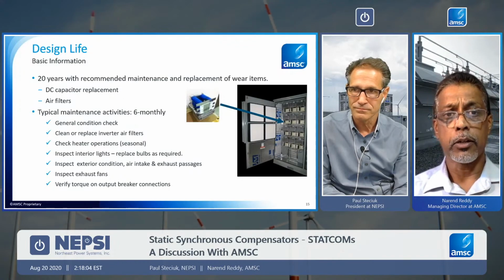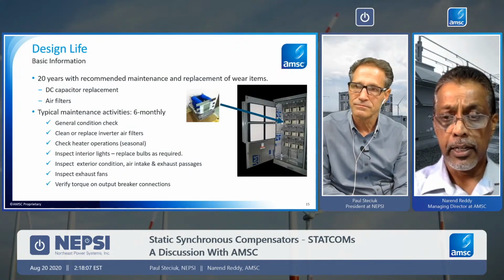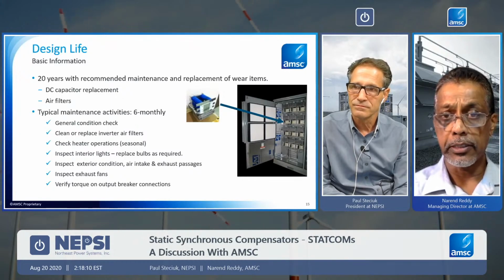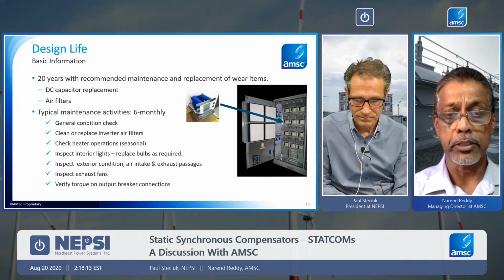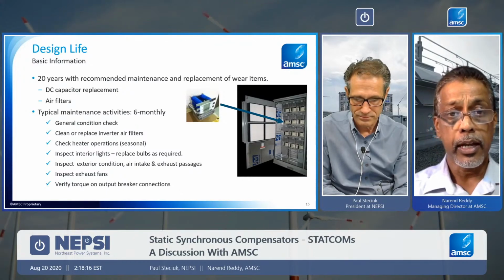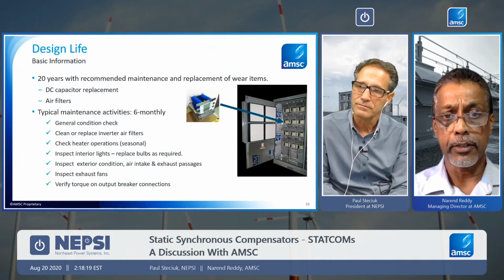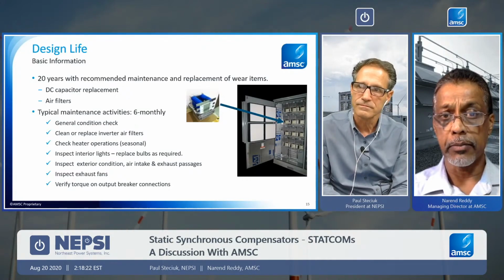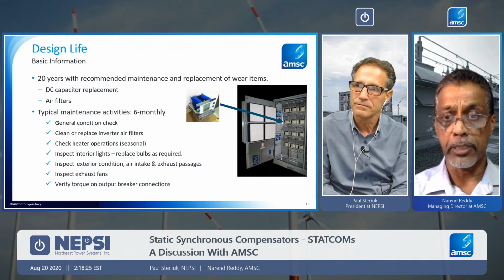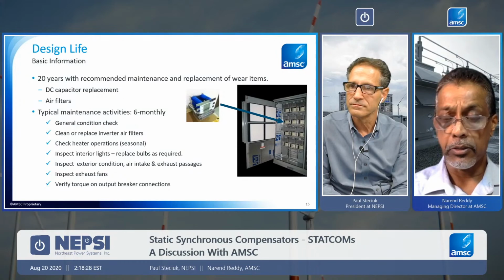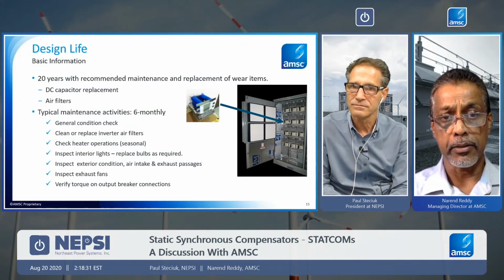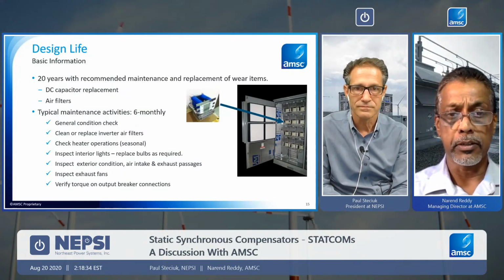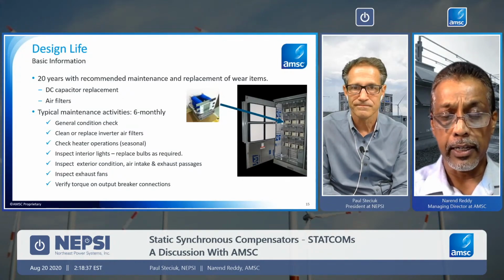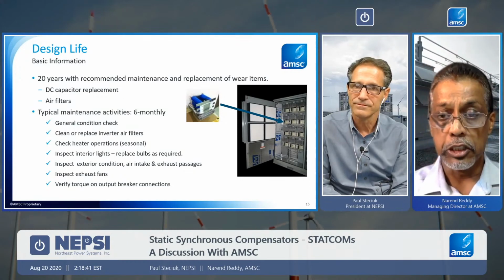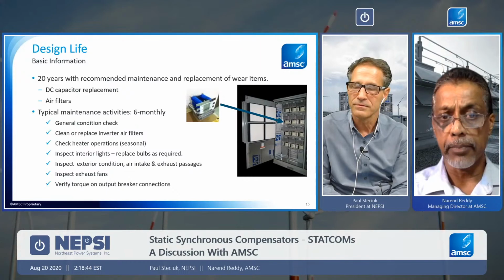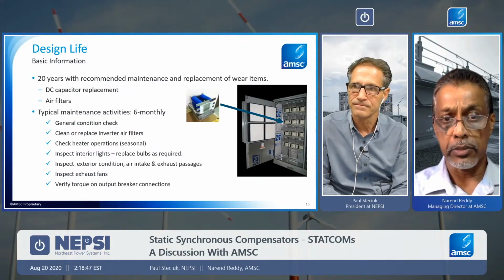In terms of design life, we recognize that this is a very common product that's going to go in utility substations. Utilities are going to own these substations and some of this equipment at some point. We designed this with a 20-year design life in mind. Some of the recommended maintenance and replacement is that the DC capacitors do require some replacement over the 20-year period, once or twice maybe, depending on how it's being used. Air filters are required to be checked and replaced as needed, but typically on a 6-monthly to yearly schedule.